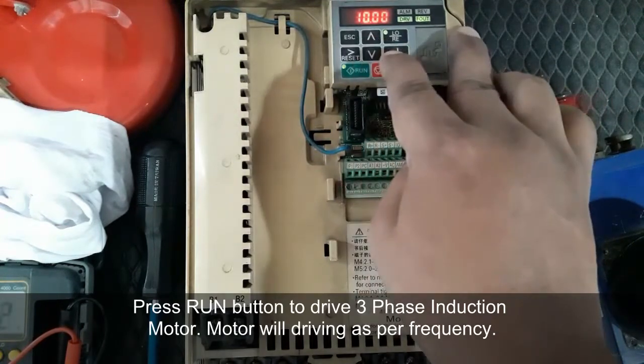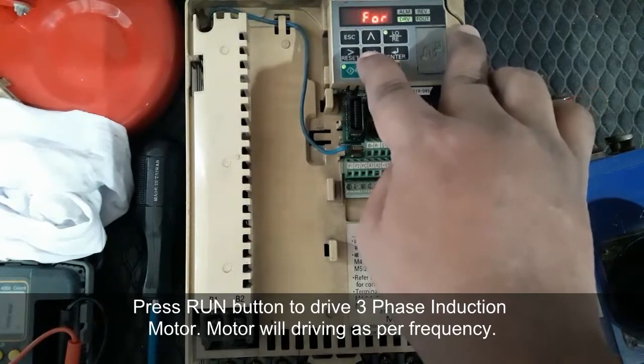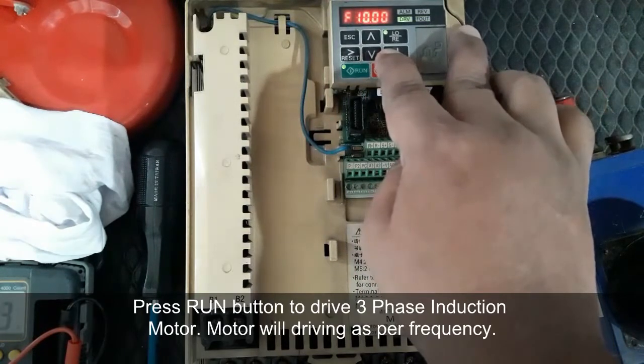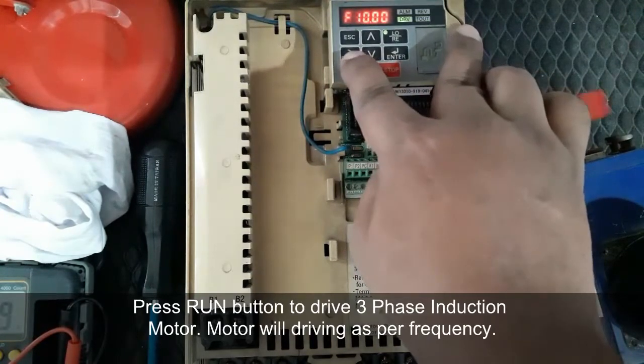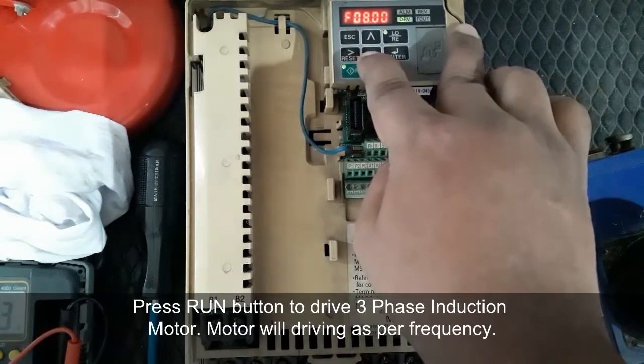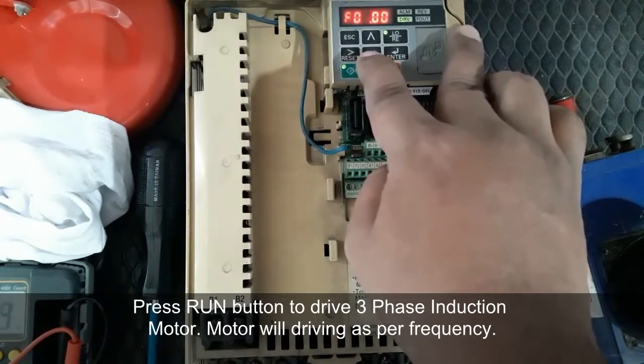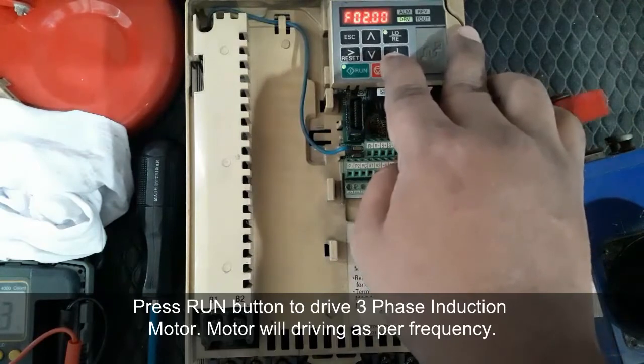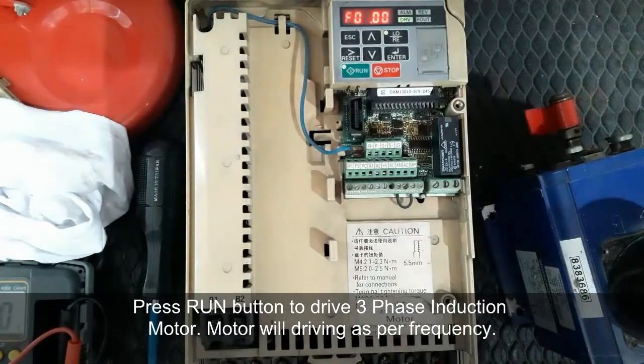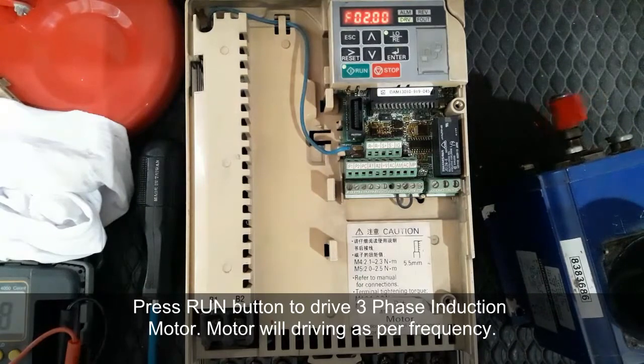So we want to check the motor rotation at 2 Hz, whether there is any problem or not. So set frequency 2 Hz. Frequency is now 2 Hz and the motor rotates smoothly as per 2 Hz for a 4-pole motor.